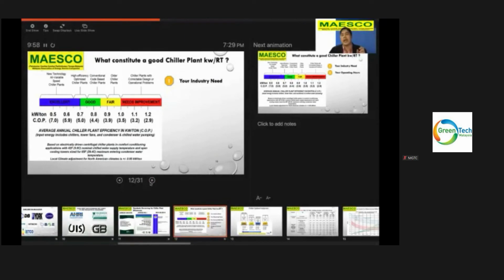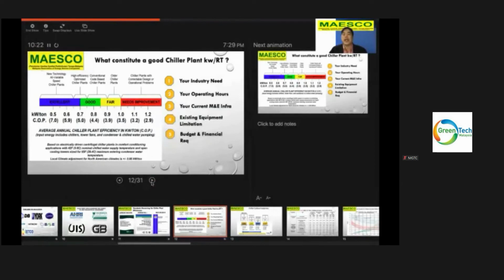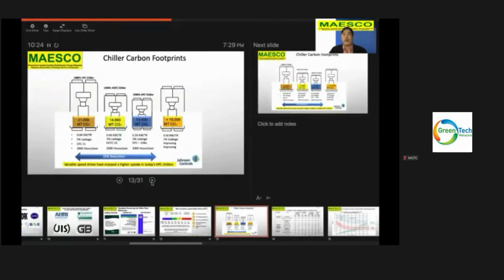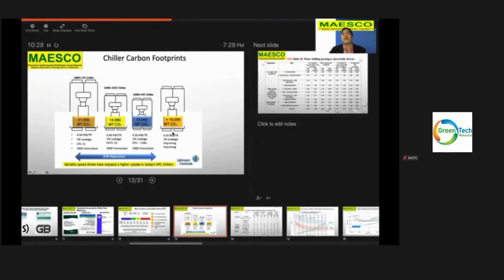Bear in mind that you must suit the chiller selection to your industry need. For example, let's say a hospital has a very high load disparity. You may use a very high load at one time and very low load at the other. Or a hotel, it's the same thing. And you must look also at your operating hours, your current M&E infra, your existing equipment limitation, your budget and financial requirement. Bear in mind, every chiller, the operation itself, has carbon footprints.